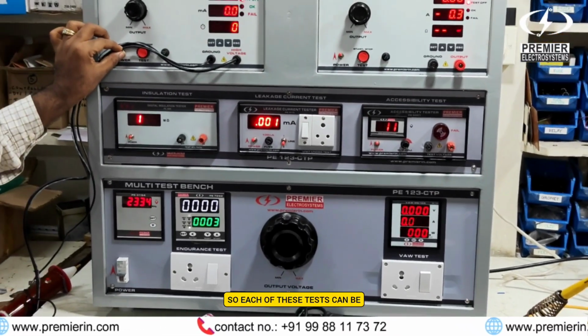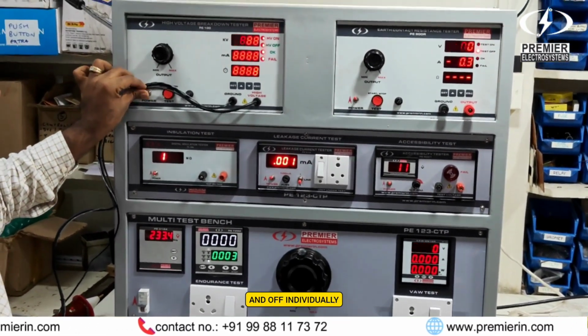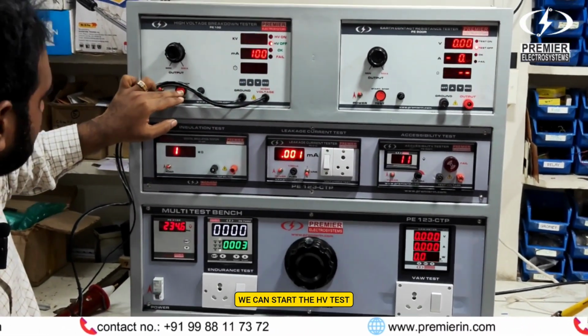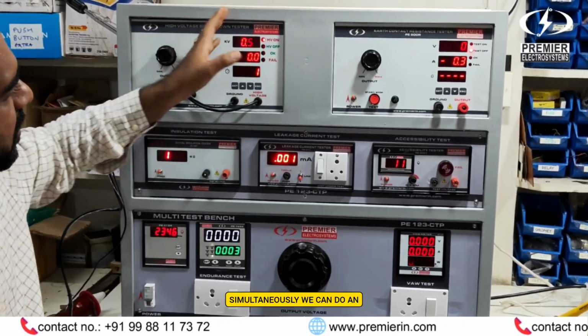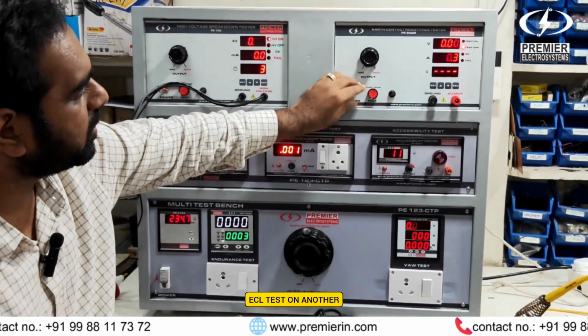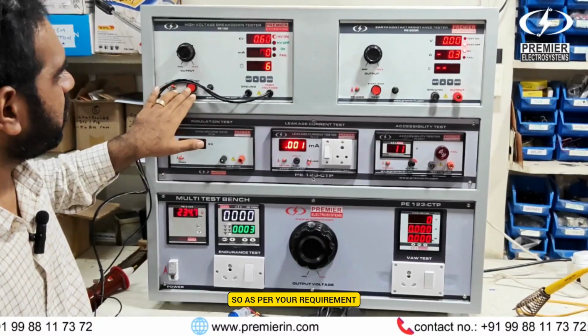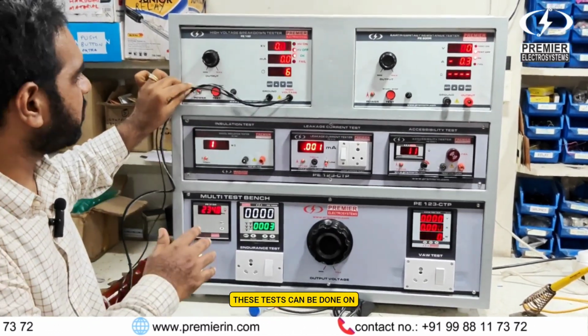Each of these tests can be switched on and off individually. As you can see, we can start the HV test from here, and simultaneously do an ECR test on another instrument. So as per your requirement, these tests can be done on separate units.